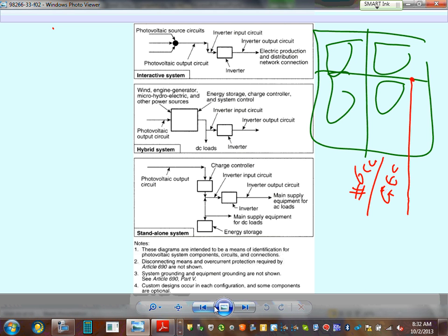So you take that conductor and take it all the way to your panel, or to the grounding electrode system in your building. So you put a number 6 copper conductor, tie the frames at multiple locations, and take it to the grounding electrode system. Or they take it typically to the inverter, on this side. If you're outdoor and you have solar photovoltaic system, you are supposed to drive a ground rod. So if you have panels in your backyard, you're supposed to drive a ground rod right next to them and ground them to the ground rod.